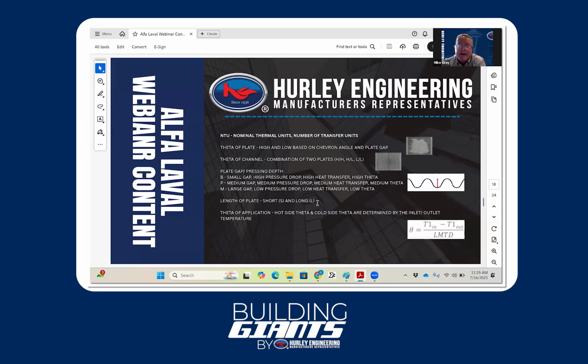It's all determined by your inlet and outlet temperatures that Dave discussed, and the log mean temperature difference as we're doing it. From that, Alfa Laval will select a specific combination for your configuration, and it'll give you many options too, which is nice. So a combination of the length of the plate, the pressing depth, and these theta channel options give you a lot of variability, a lot of combinations.